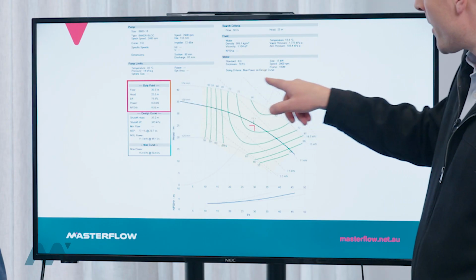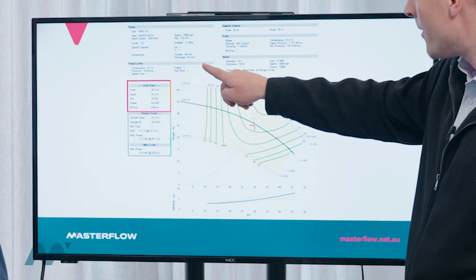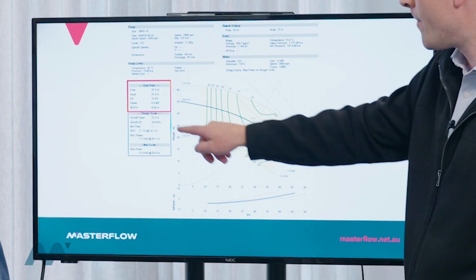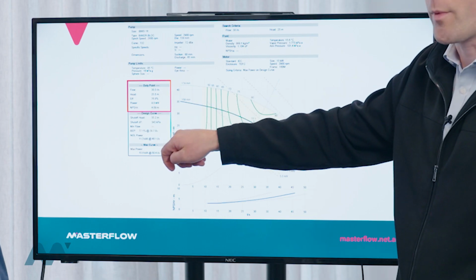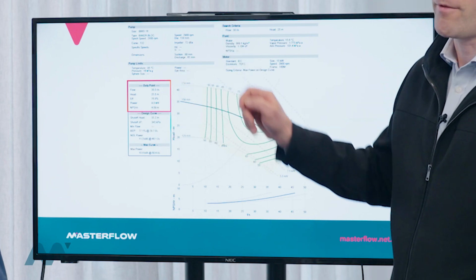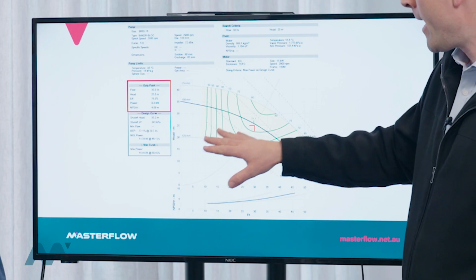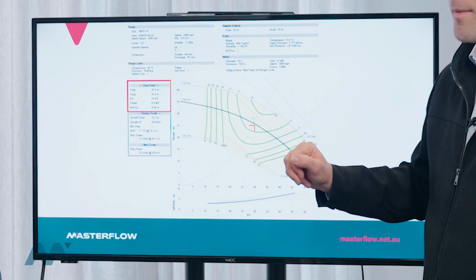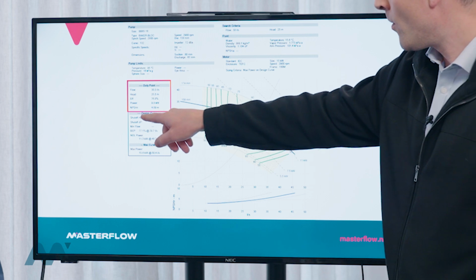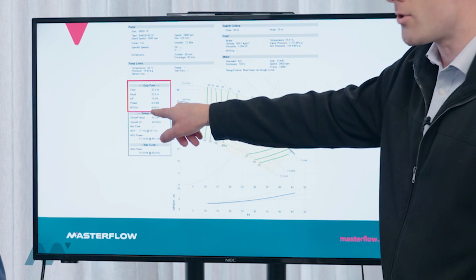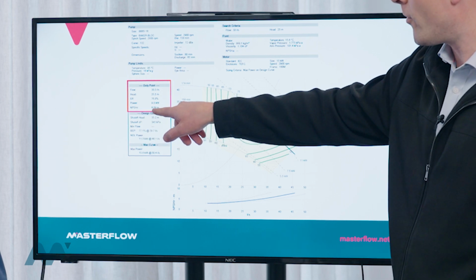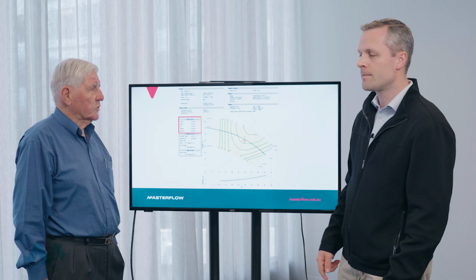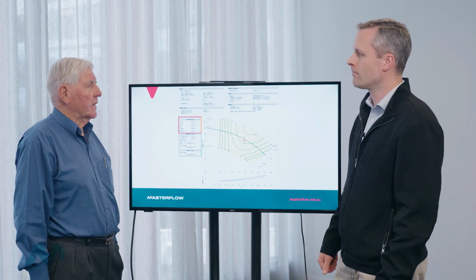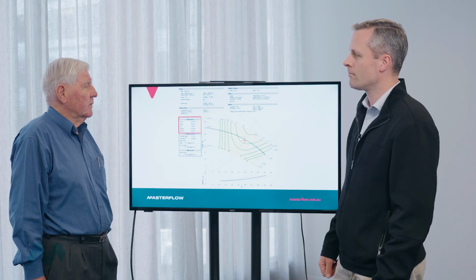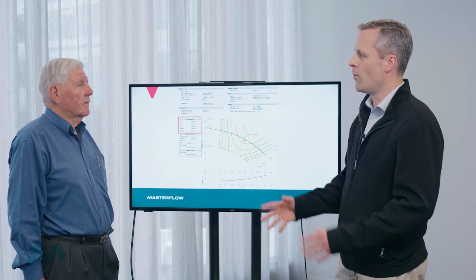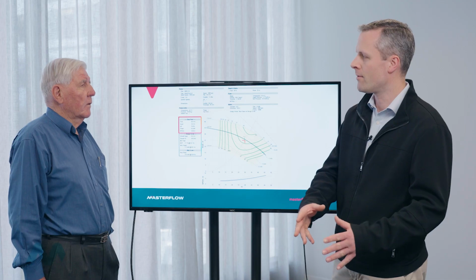So with a 2,900 RPM pump, the speed is given up here, 2,900 RPM, our net positive suction head required will be much higher than on a 1,450 RPM pump. Had a 4-pole pump been requested and supplied, we would not have had this issue because this figure would have been much less. Yeah, well, that's a function of pump speed, isn't it? NPSH performance is related to the speed of rotation of the impeller. So the less the speed, the smaller the pressure required.